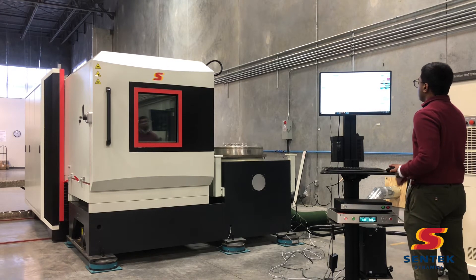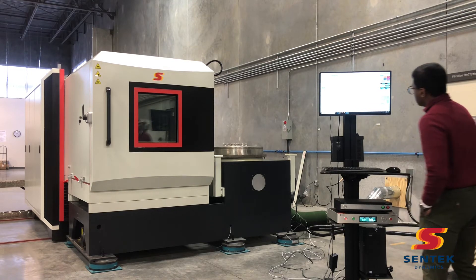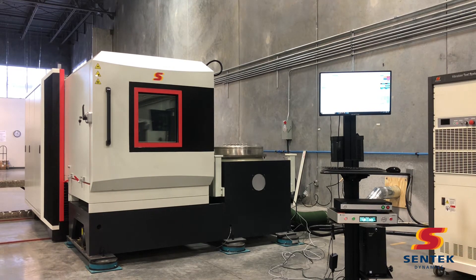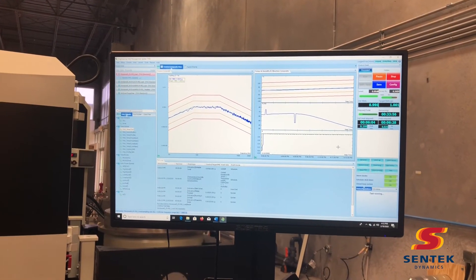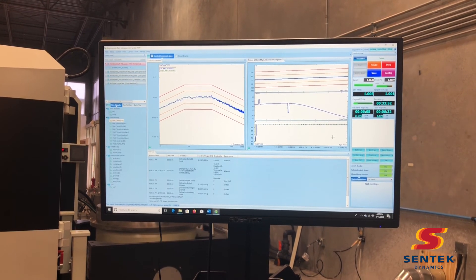This entire THV system from Sentek Dynamics is controlled by the Crystal Instruments Spyder 81 vibration control hardware and the Crystal Instruments Spyder 101 environmental chamber control hardware. These instruments are integrated into a single software application.